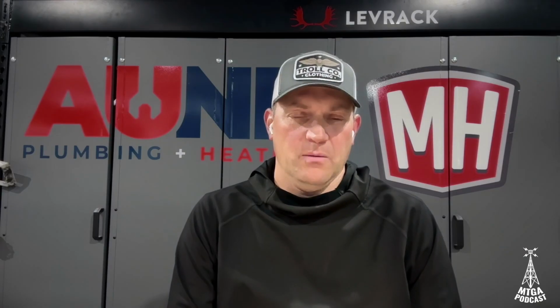Because what I was ultimately trying to do, I'm just going to be honest with you, was avoid using copper for the expense. If I had to go to copper at 1.25, because 1 inch wasn't going to do it, we're not bending copper around corners and sweeping around big long radiuses like we could with the PEX. Then copper was going to get expensive because we were going to start getting big. And the fittings, it all adds up. Takes more time. It's harder to install.